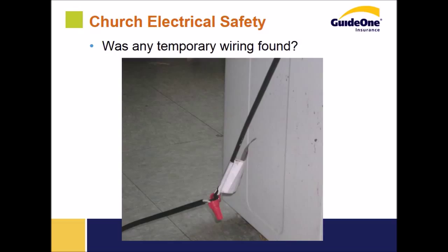Here's just a picture of some temporary wiring. They've actually hardwired a dryer, in this case a clothes dryer, to power it, and this is a condition that can lead to all kinds of problems. So if you find any temporary wiring, any exposed wire nuts, or conditions that could cause a problem, we need that reported as well.